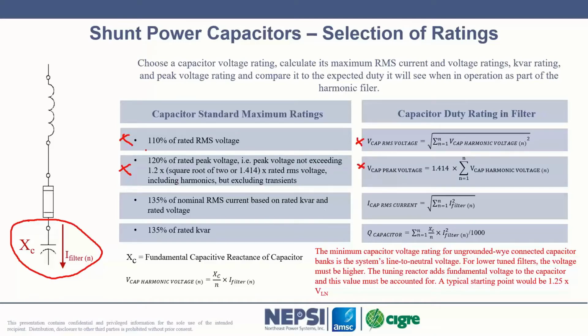And the standards dictate these values that are allowable for a given capacitor. So this is the way we make choices. Basically, in our spreadsheet tool, we actually use a flagging mechanism. We will not exceed these values, okay, in the design for the maximum current. And again, the maximum current being a very conservative current that we have chosen for the design. That's the philosophy that should be followed.